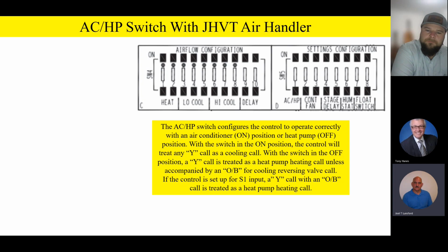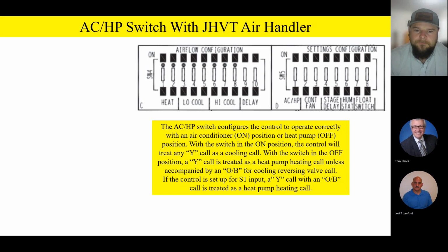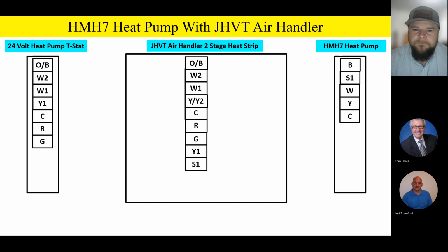And then the whole lesson for all of this is the fact this air handler does not require any kind of relay kit, but we've got to set it up on the board to make sure that it knows it's looking at the HMH7. Or if you put it on a regular heat pump, you've got to let it know it's on a regular heat pump as well. So any questions or comments on that before we jump into the block wiring diagram? Good shape? All right. Okay, let's go ahead and take a look at this block wiring diagram.